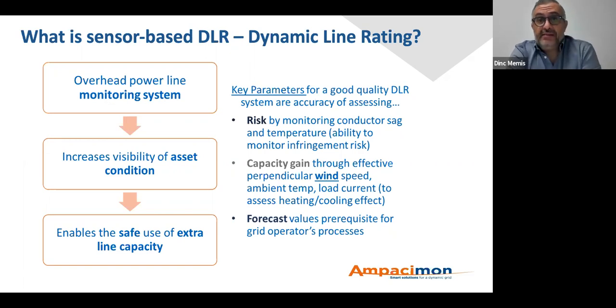What is sensor-based dynamic line rating? Sensor-based dynamic line rating is a system of overhead line sensors installed to measure conductor and real-time environmental data, first to monitor the overhead power line. Once the monitoring is happening, the next stage is providing more accurate visibility of the asset condition, in this case the overhead line. Then, once these two steps are completed, we move to the last stage, which is to determine the true extra capacity available on the existing line within its safe use limits.